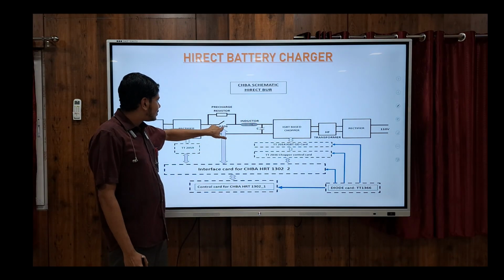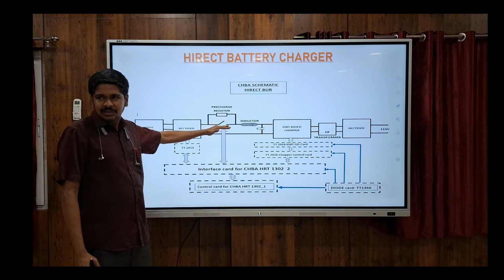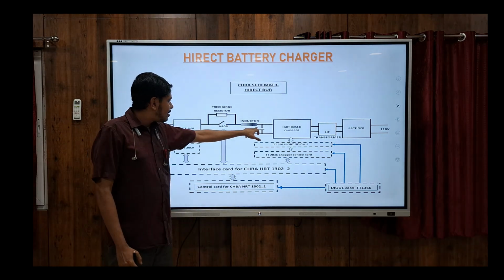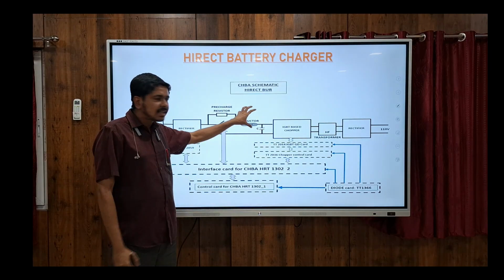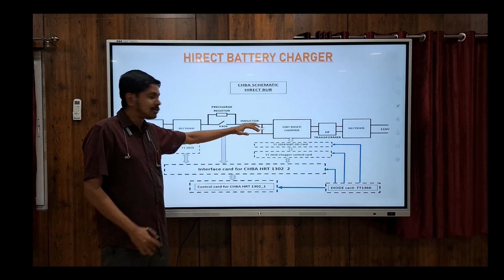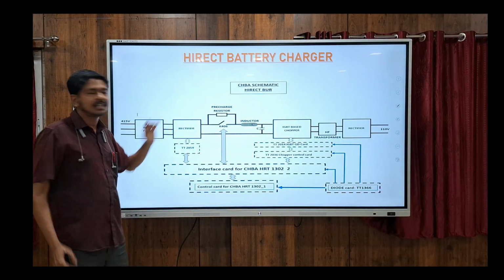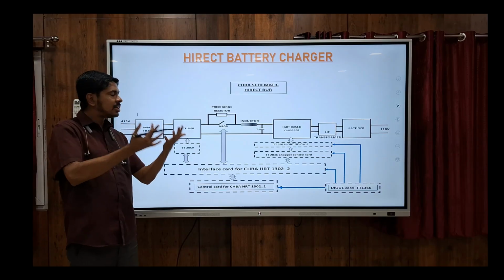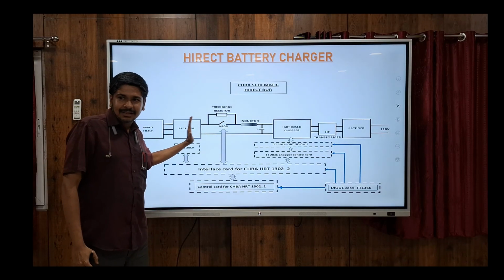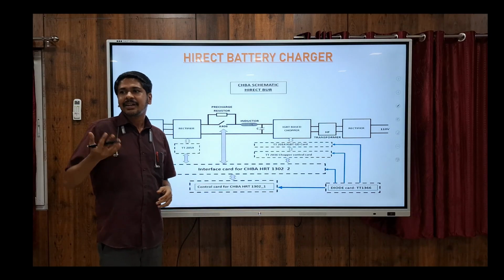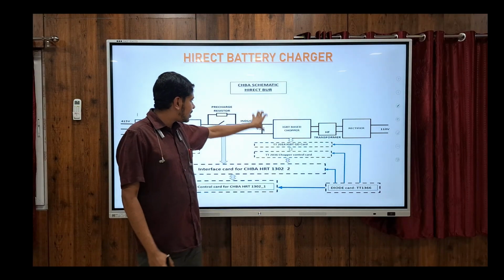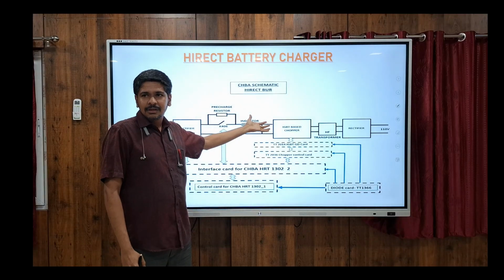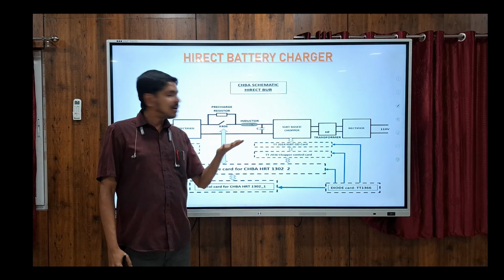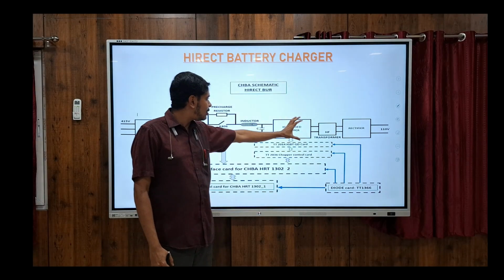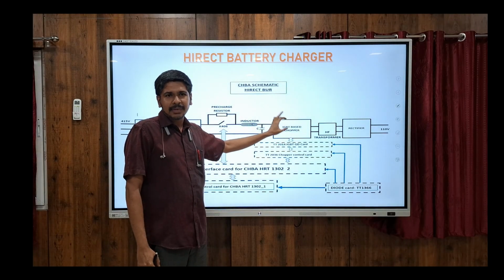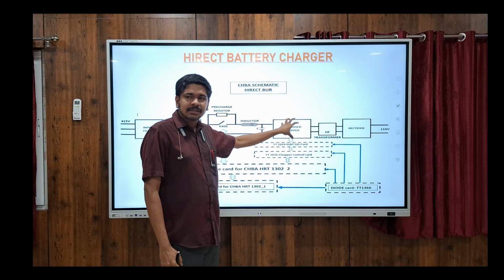After that, the K406 contactor is closed. By then some voltage has already been built up through the pre-charge resistor, so the terminal voltage difference between the two ends is little less, the inrush current is limited, and it works smoothly without any inrush problem. Then we get a high value DC, more than 500 volt, and it has to be stepped down using an IGBT based chopper, which will be having some IGBT.